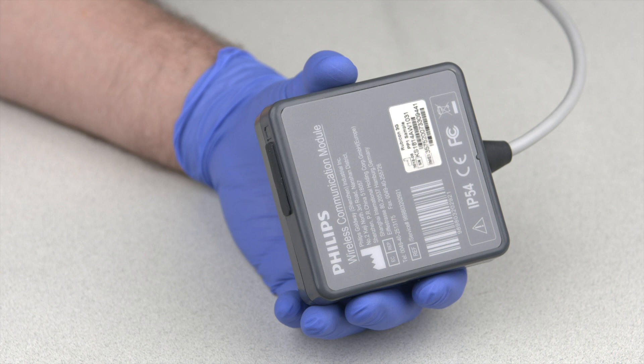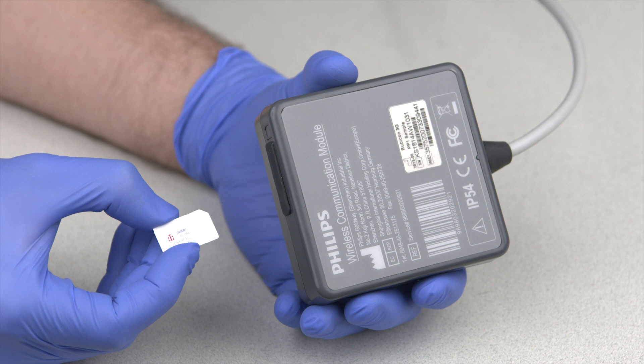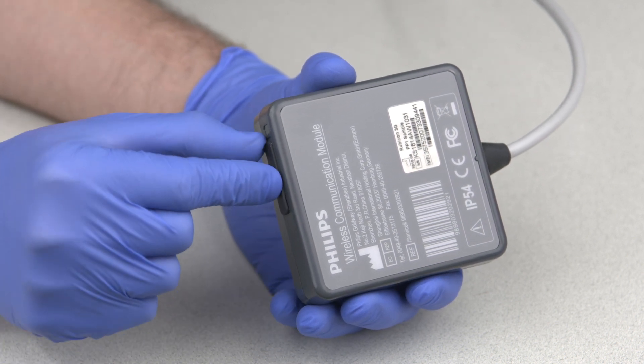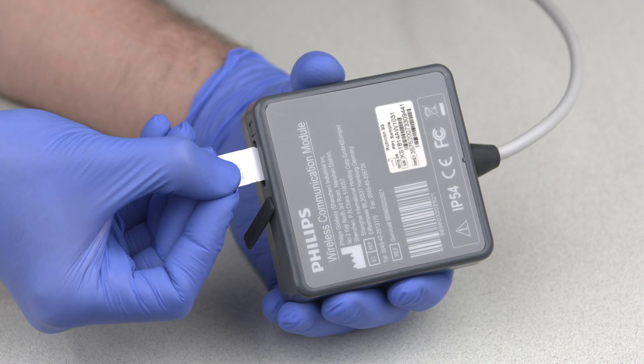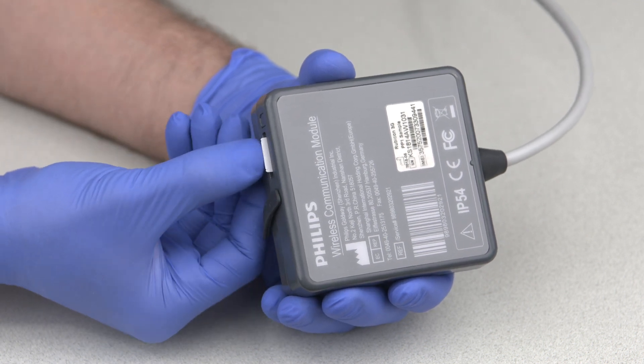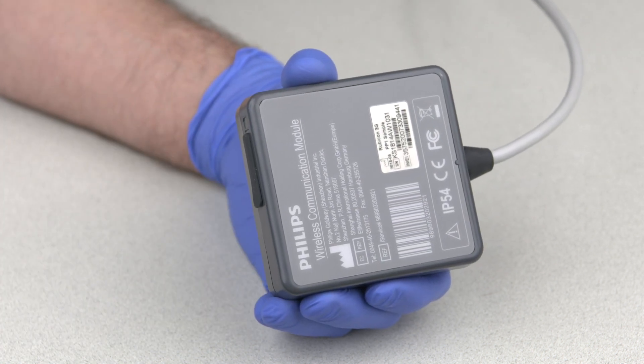To operate on cellular mobile networks, the Communication Module must have a SIM or Subscriber Identification Module card from your local cellular mobile network provider installed. To install the SIM card, open the rubber plug to access the SIM slot. Orient the SIM card and push it into the slot until it is fully seated and latches, then close the rubber plug.